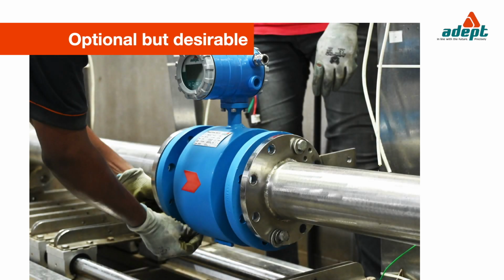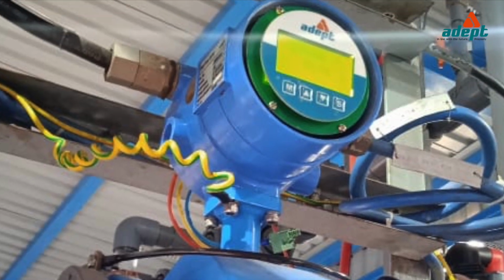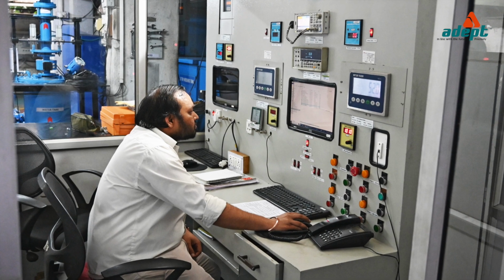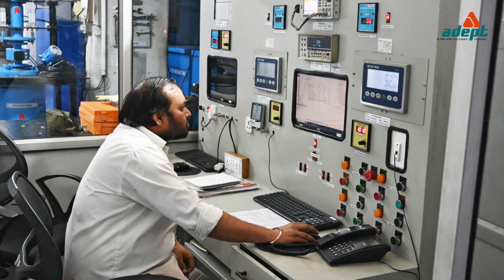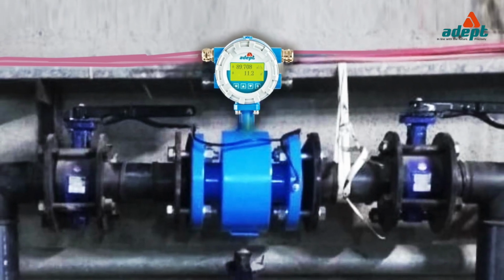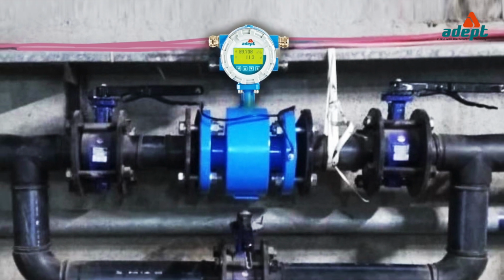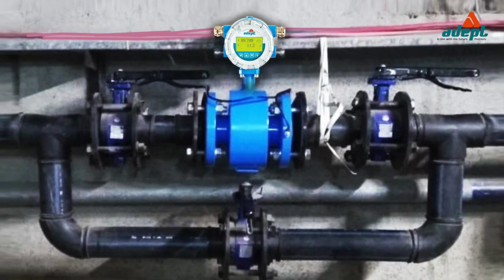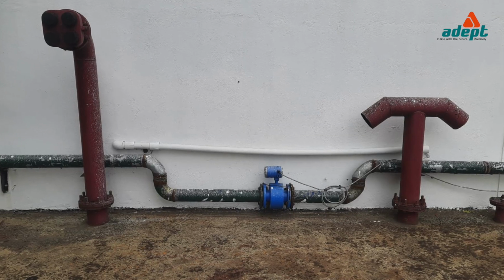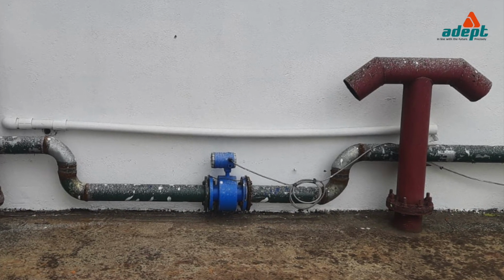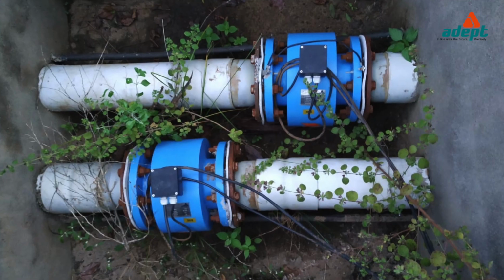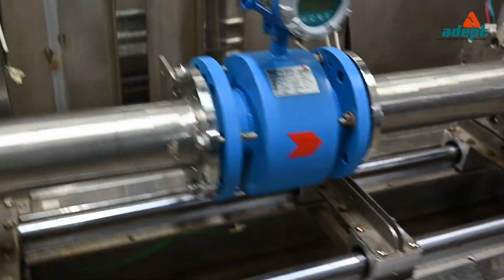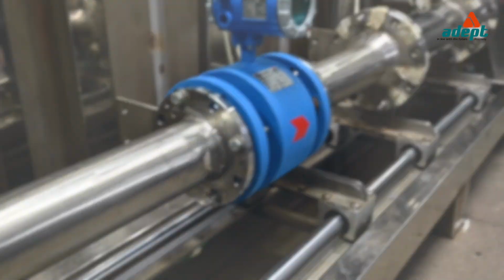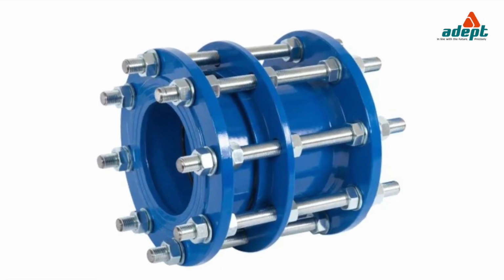Optional but desirable. Flow meters of sizes up to DN300 generally require factory calibration, so a bypass arrangement can be provided for easy removal and reinstallation. For flow meters installed at outdoor locations or underground pipelines, suitable size chambers can be constructed around the flow tube for safety and for easy maintenance. At such installations, the flow meter can be provided with a dismantling joint.